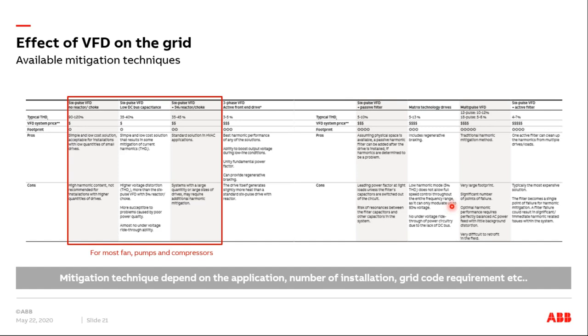So that's one way, the I square R loss. But harmonics are also created at higher frequencies, so you are creating more AC losses, more frequency related AC losses, both in your conductors, for example on the transformer, and on your transmission line, because at higher frequency you are not accounting for the added skin effect losses. So from the grid side, I would be most concerned about the transformer and the related circuit breakers used with the transformer. Yeah. Does that answer your question? If you have anything more specific, I would be willing to answer it.